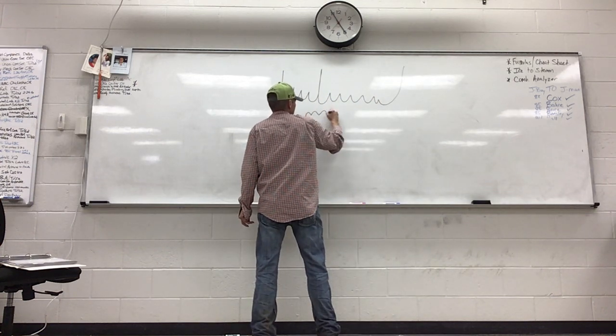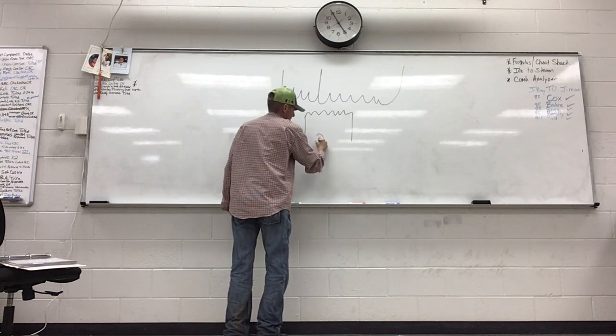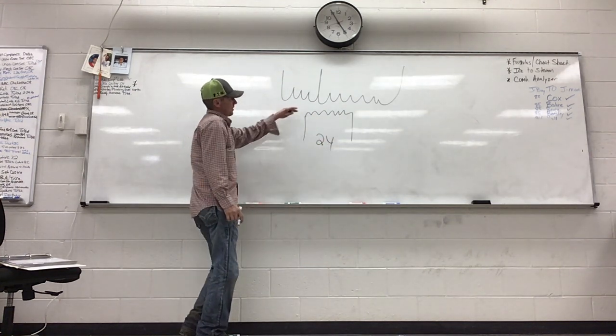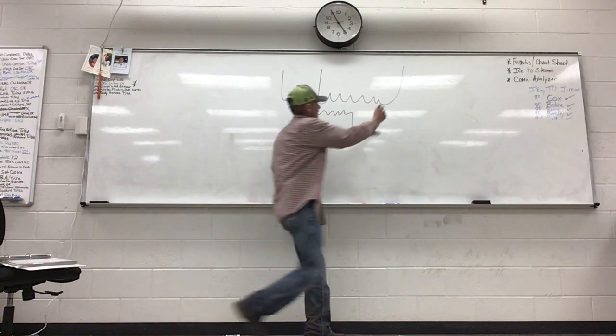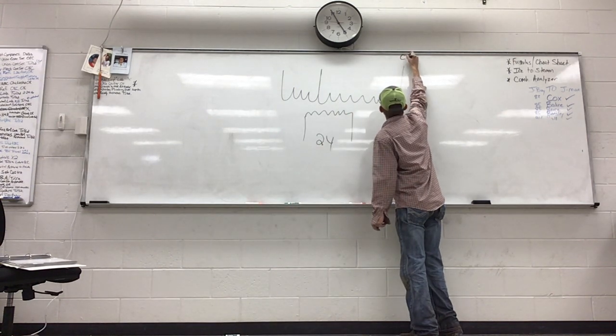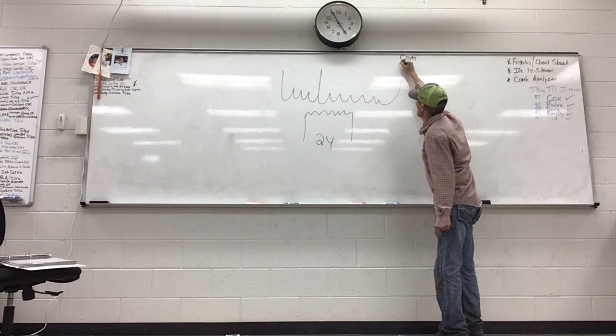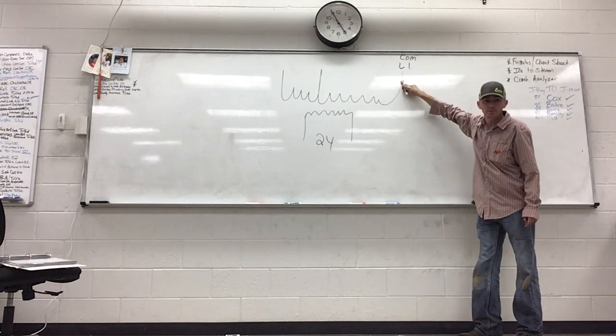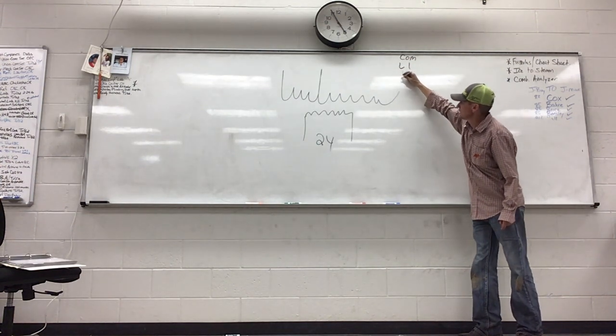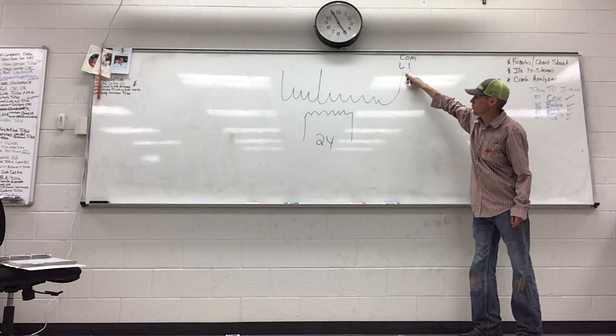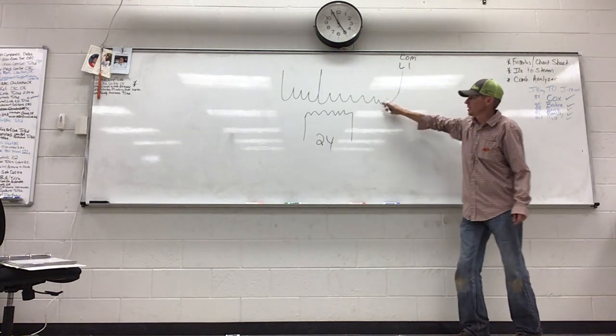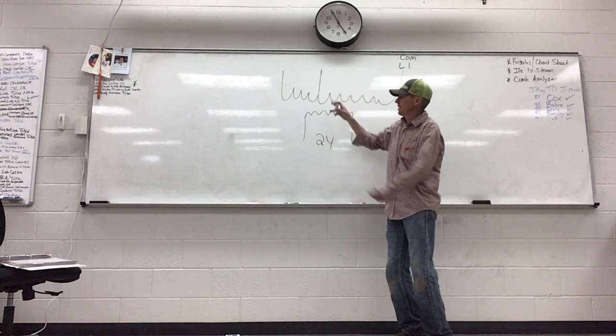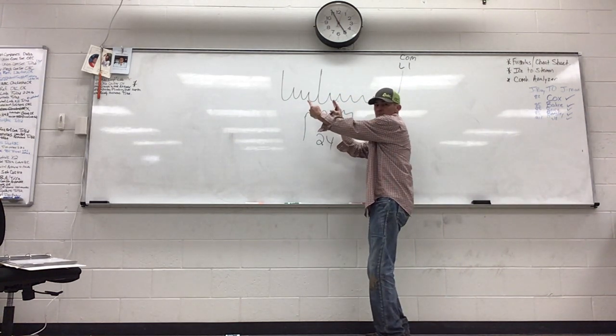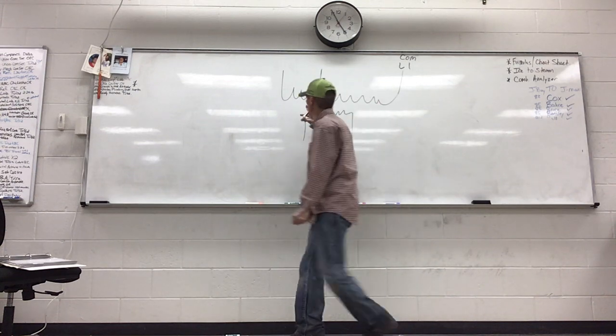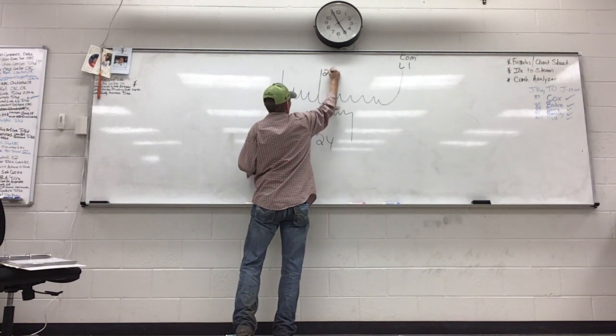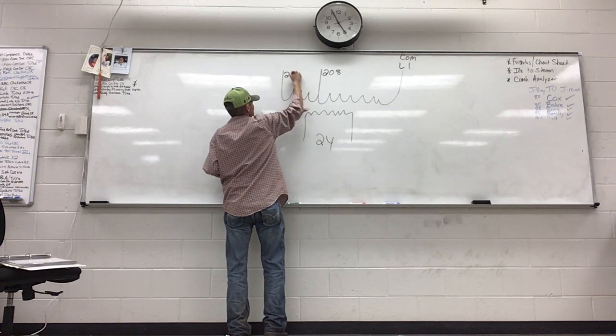Artist rendering here, hang on. This is my 24 secondary. But what I got going on up here is I have a common tap right here. So on this common tap, I'm going to take L1, I'm going to feed this primary. So, I erased it, my bad. So L1 comes in and feeds this primary. It goes in and feeds the primary. And then I've got two possible options for L2. This is going to be my 208 tap. This is going to be my 240 tap.